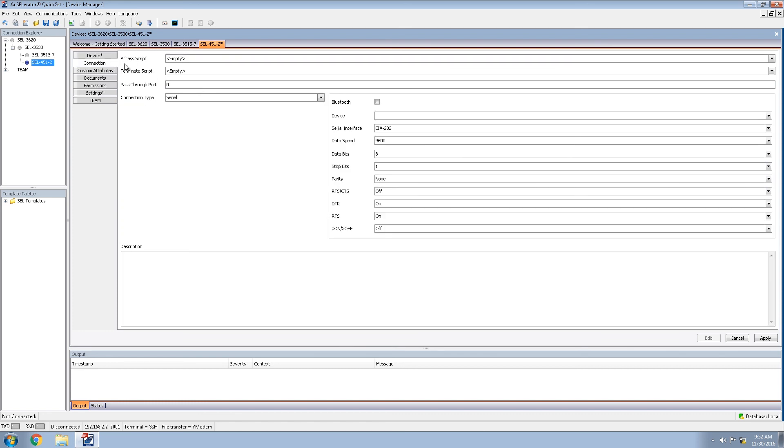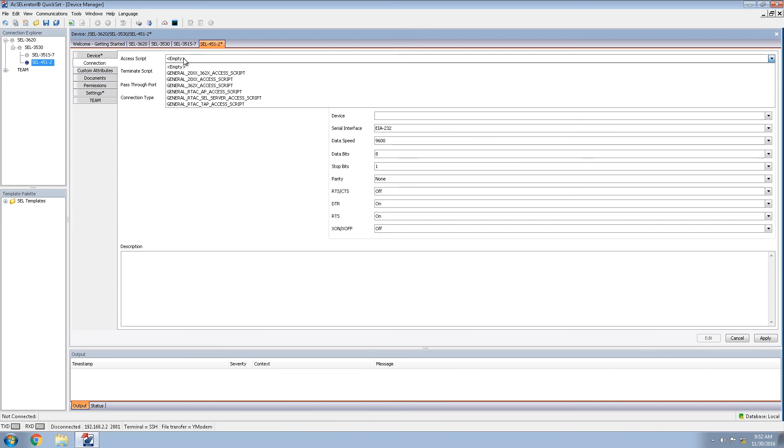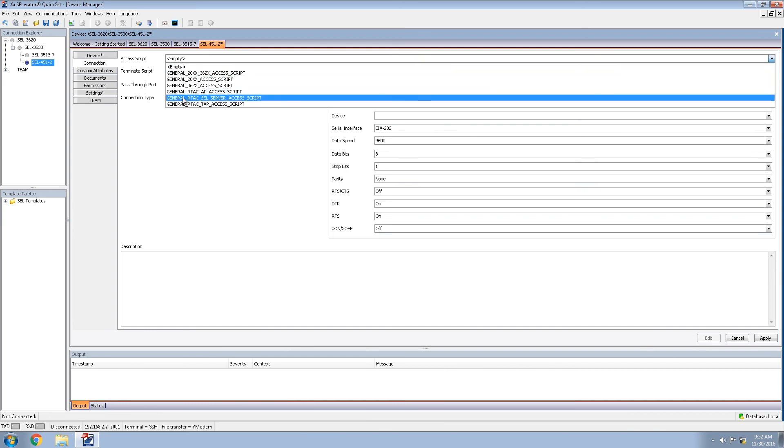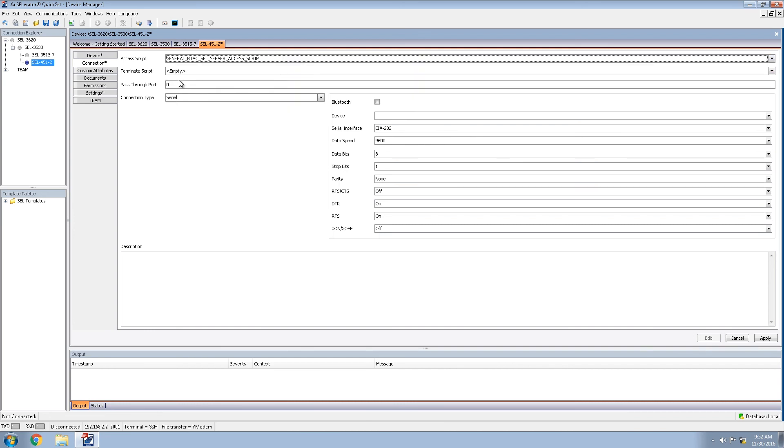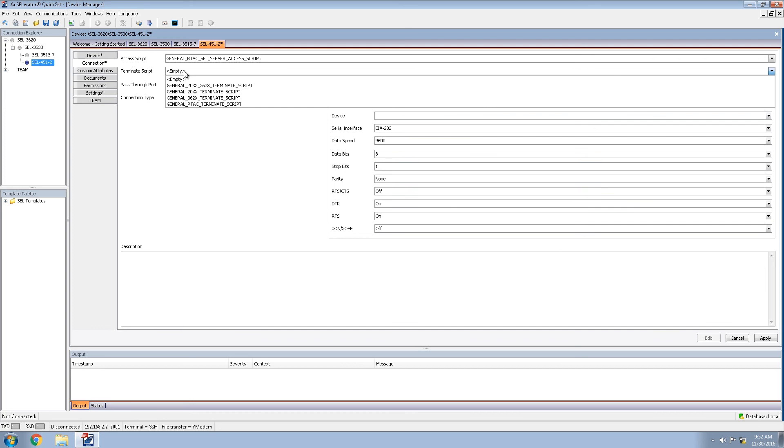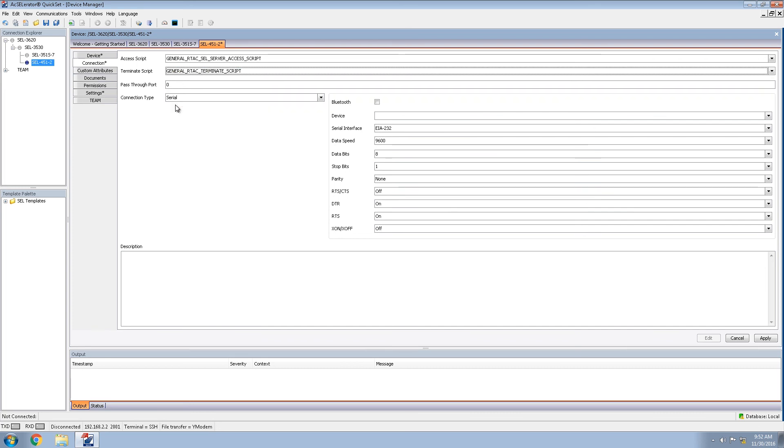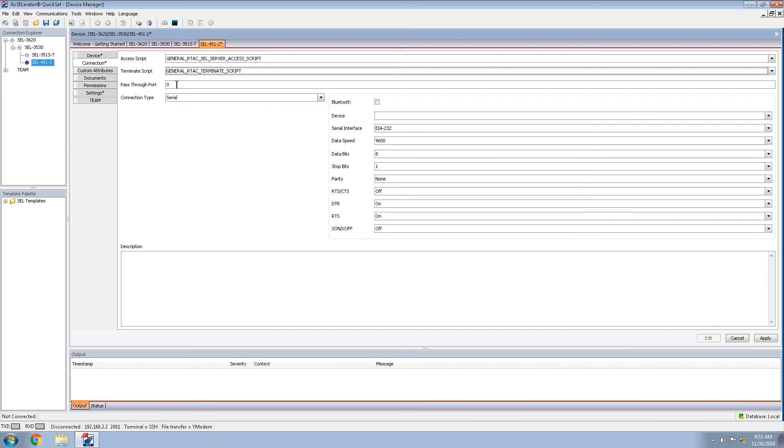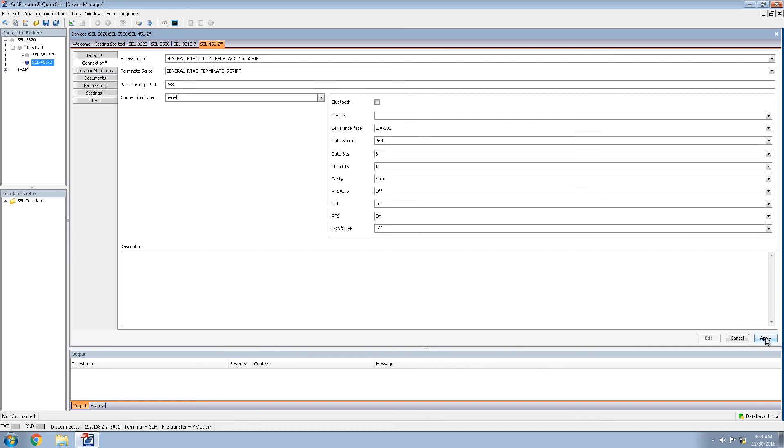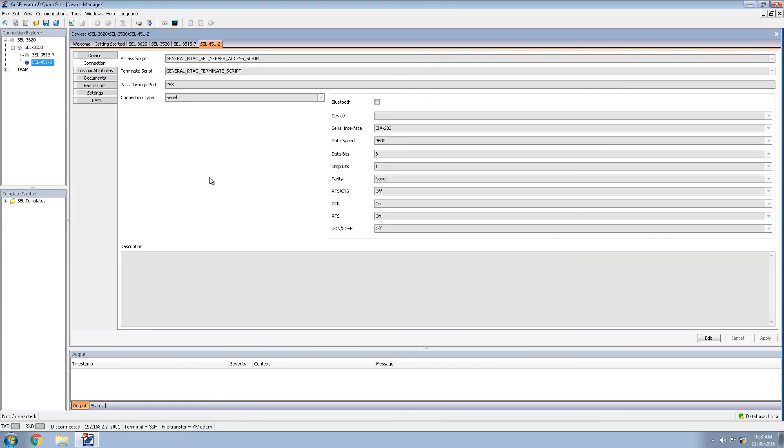For the connection type, we will again select access script, general RTAC SEL server access script. For the terminate script, we will again be choosing the general RTAC terminate script. The pass-through port here, we will be using 253. Again, we will be discussing how to come up with this port setting in a later video. And again, the connection type does not matter because it is on the backside of the 3530. Click apply to save our settings.